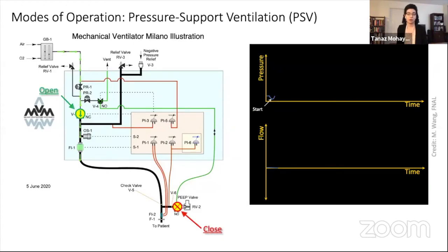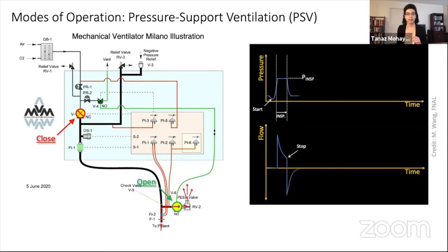In MVM, at that point, the expiratory valve shown in red closes and the incoming airflow valve shown in green opens to allow medical air to flow into the patient's lungs. Note that the inspiratory time finishes when the flow shown at the bottom drops below a given fraction of the peak flow. At that point, MVM valves change state again: the expiratory valve opens, shown in green, and air flows out of the patient's lungs and vents out through the PEEP valve. At the bottom, MVM also closes the incoming airflow valve, shown in red, to prevent any flow of air to the patient.